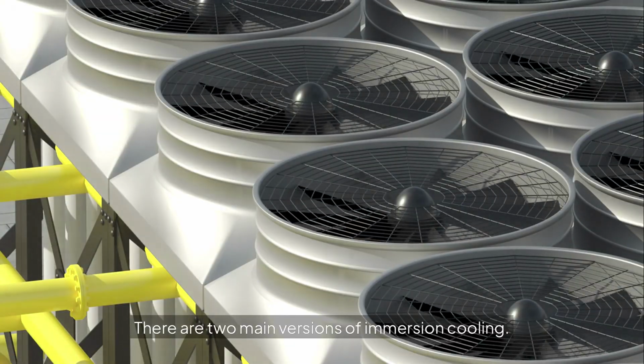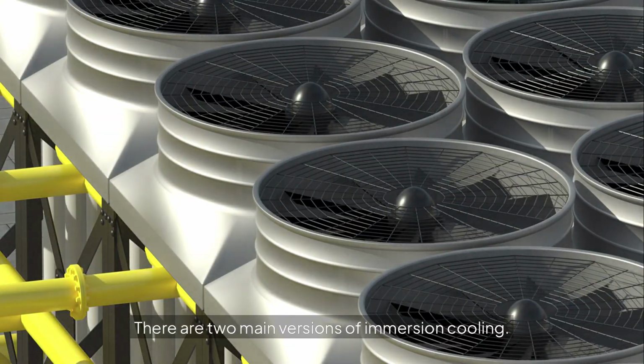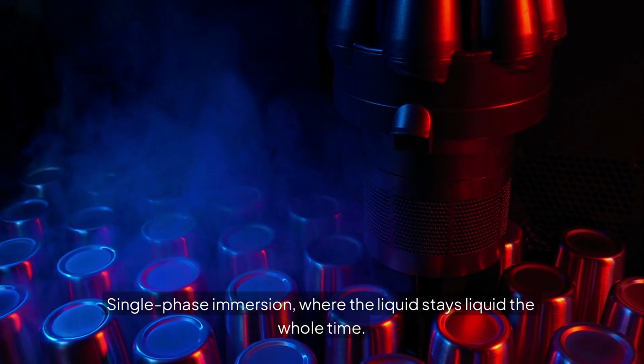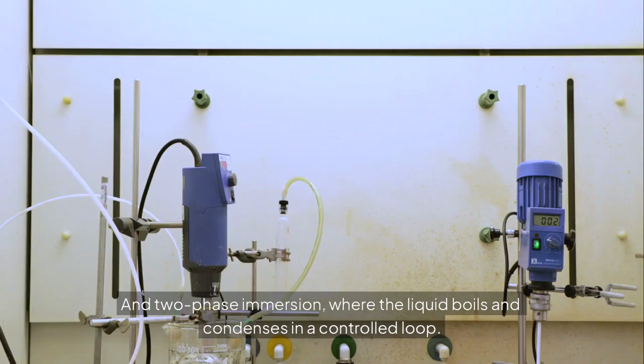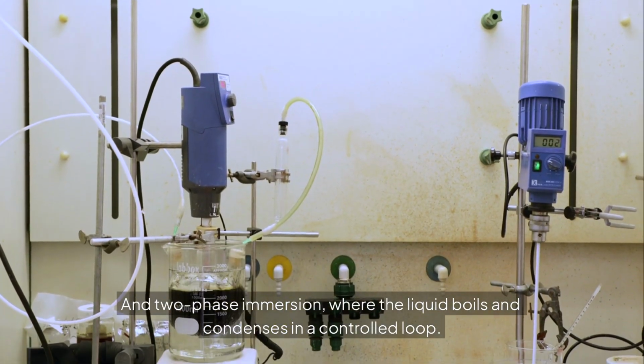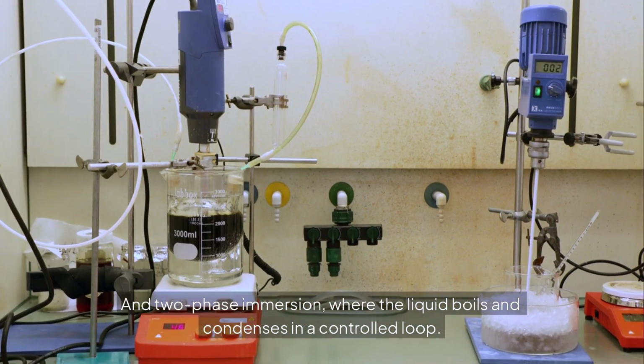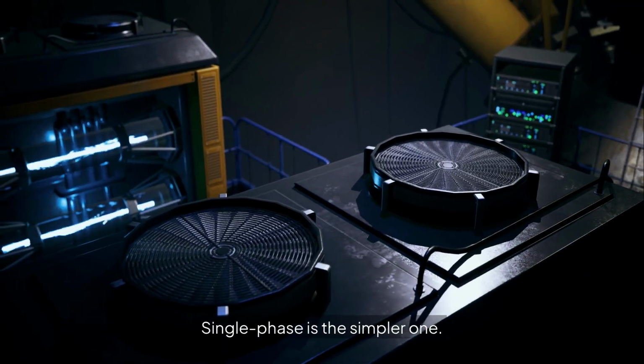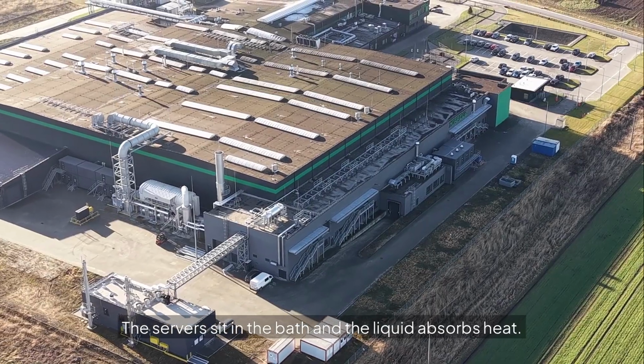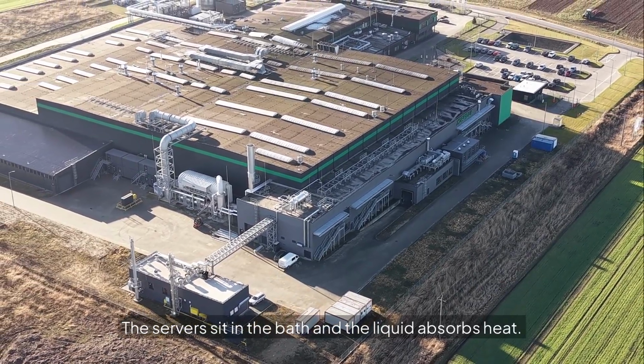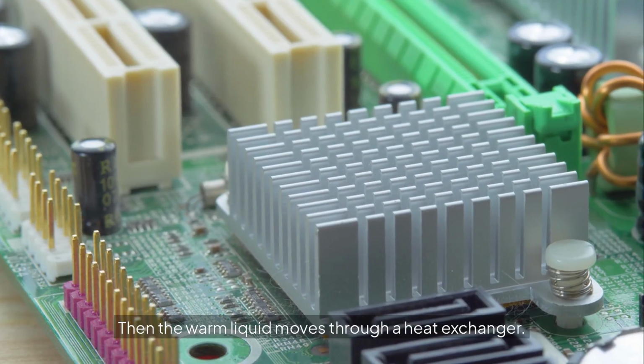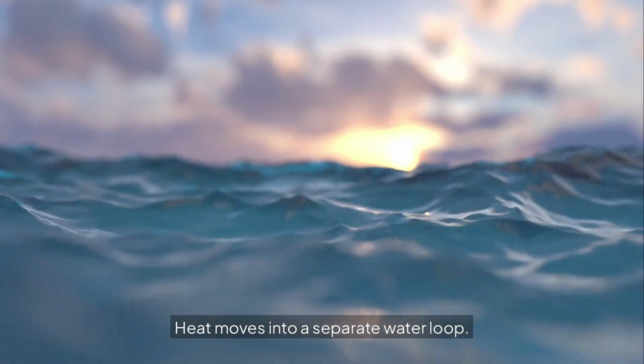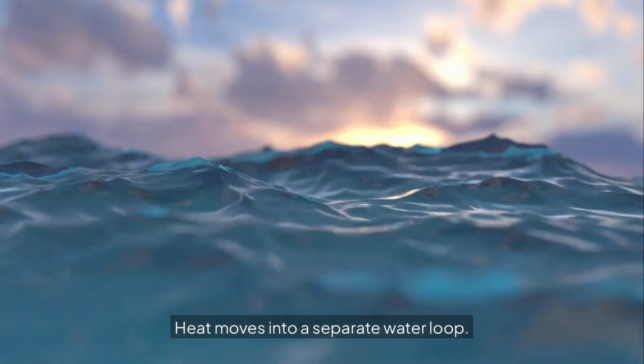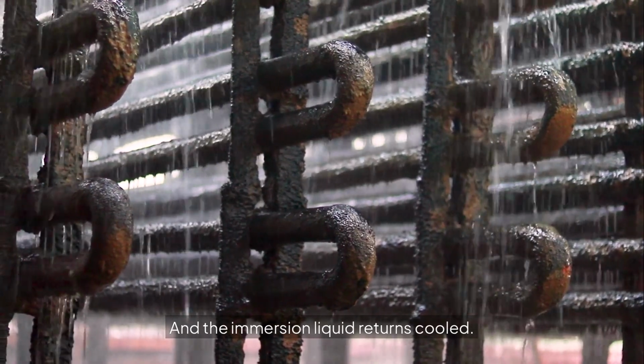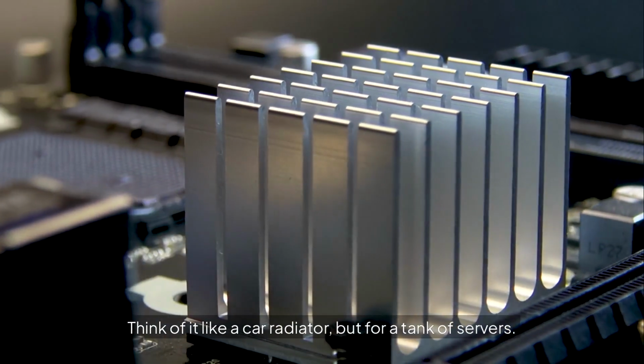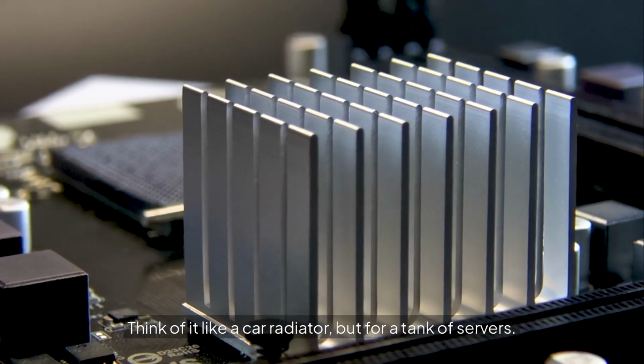There are two main versions of immersion cooling. Single-phase immersion, where the liquid stays liquid the whole time. And two-phase immersion, where the liquid boils and condenses in a controlled loop. Single-phase is the simpler one. The servers sit in the bath and the liquid absorbs heat. Then the warm liquid moves through a heat exchanger. Heat moves into a separate water loop, and the immersion liquid returns cooled. Think of it like a car radiator, but for a tank of servers.